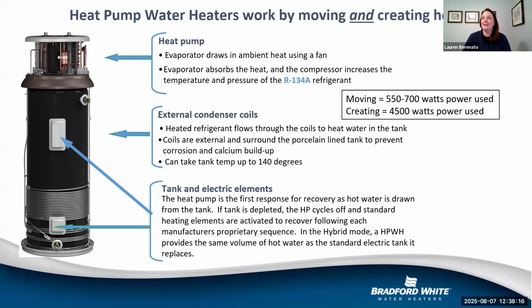If you look at energy code here in the United States, I'm assuming it's the same in Canada, you are told to turn your pump off at night in commercial buildings to not have your water recirculating. If you look at OSHA, which is basically our government agency that oversees that workplaces are safe, they say do not turn the pump off, because then you are subjecting your employees to Legionnaires' disease exposure. So it's something to be mindful of, and where you recommend, say, water heaters should be stored at 140 degrees and go from there, just to cover your end of it. That would be my recommendation.